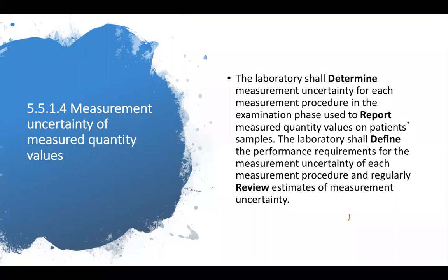On the basis of our control result, standard deviation is 0.2, and measurement uncertainty is 0.4, 0.2 multiplied by 2. So whatever we are reporting, if it is 22.4, we can tell you with 95% certainty it is not beyond 23.